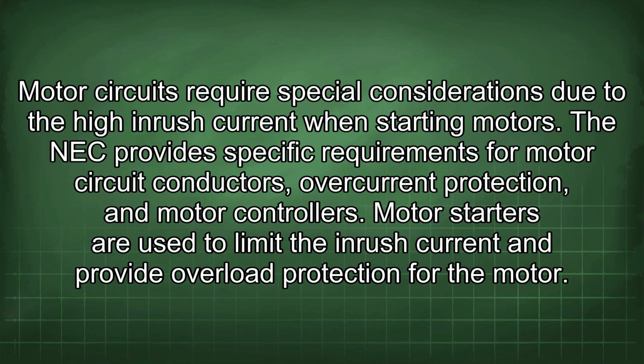Motor circuits require special considerations due to the high inrush current when starting motors. The NEC provides specific requirements for motor circuit conductors, overcurrent protection, and motor controllers. Motor starters are used to limit the inrush current and provide overload protection for the motor.